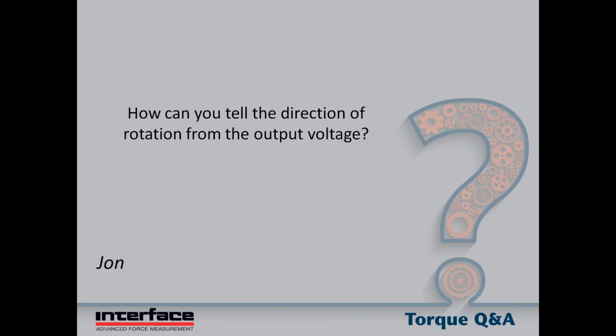Yes. Sorry to jump in again, but the one thing I would point out here is, I guess you can make an approximation of the direction of rotation if you're running at what amounts to basically a steady state condition, because obviously the polarity of the output is going to be positive in one direction and negative in the opposite direction. Again, assuming you don't have the effects of inertia involved like you described. So the basic premise of the way the torque sensor works, you have a positive output with a clockwise torque applied, and a negative output with a counterclockwise torque applied. But again, you can't use that as a strict rule because of what you described.